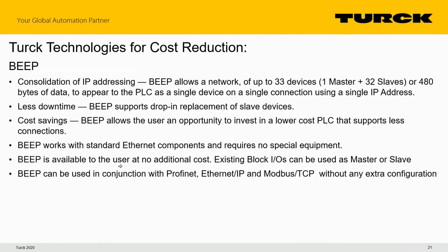So to summarize BEEP, we're looking at the consolidation of IP addressing. So we only have one IP address that is talking to the PLC and up to 32 slaves behind it. Less downtime because we can do drop-in replacement of slaves. You can also have your master pre-configured so that if the master fails, that's a drop-in replacement.